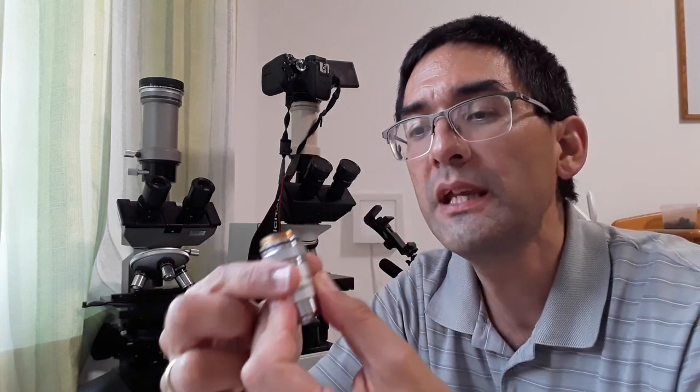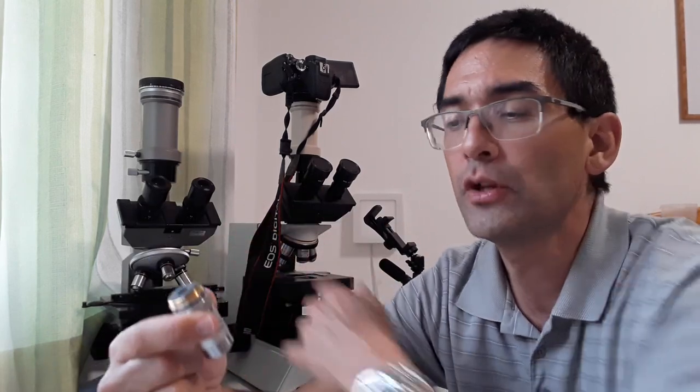But it appears that they now seem to have defined a different objective standard for making the microscopes more compact. But I just want to say that essentially it's not only the optical distance of the tube length which is standardized but also the threading here is also standardized. This means that I can actually exchange the objectives between microscopes that have the DIN 160 millimeter standard. So I could simply fit this microscope objective in either this one here or this microscope here because they are basically all the same standard. I can also exchange them.